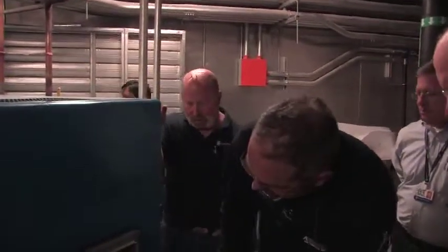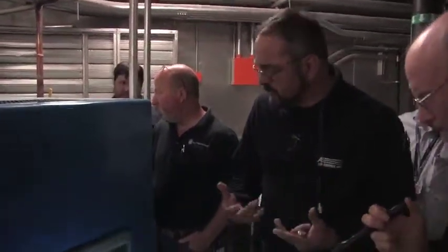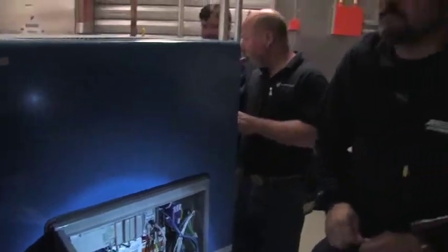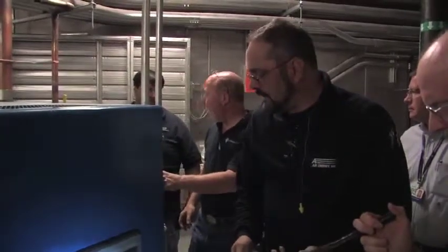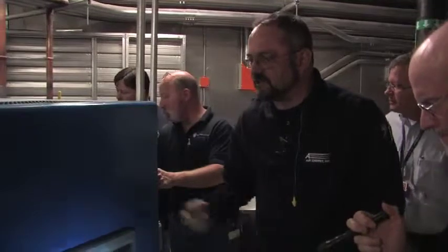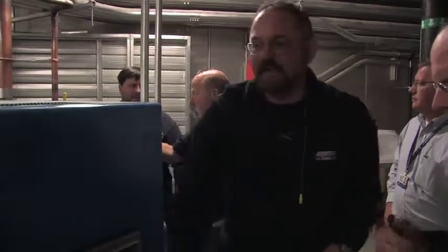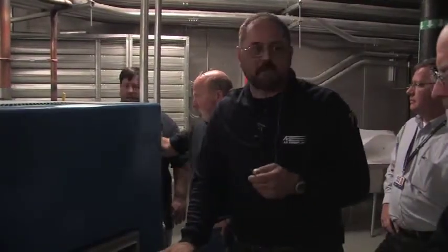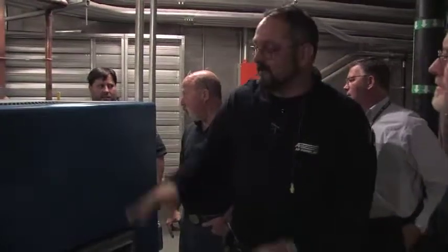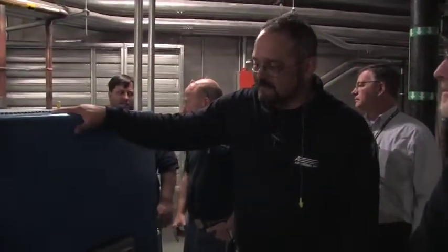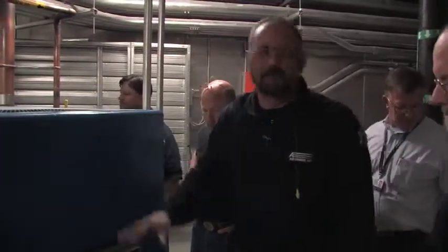Oh, and I know you're still also using the regular standard monitoring system besides the LonWorks that works off the relays. Yeah. So that's this bank of relays right here. One thing they have done in this version of the software is your OK relay, the one that says the machine's running and is all right, is now energizing as soon as you power it up, where it didn't before. So they had to wire the contacts differently. And that's to comply with the NFPA regulation that if something loses power, they want an alarm. So now if it's powered up, the downside of that is you shut it off to work on it. You're going to get an alarm. Well, right now, if they're actually paying attention to it, somebody's getting an alarm that this one's down.